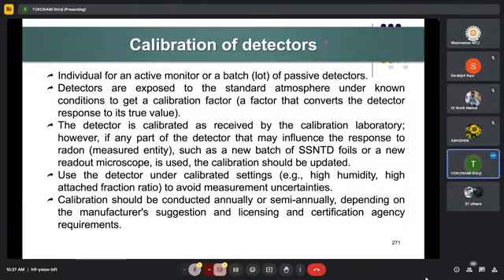For calibration of detectors, individual calibration for an active monitor or batch of passive detectors should be prepared. Detectors are exposed to the standard atmosphere under known conditions to get a calibration factor. That is a factor that converts the detector response to its true value. The detector is calibrated as received by the calibration laboratory.